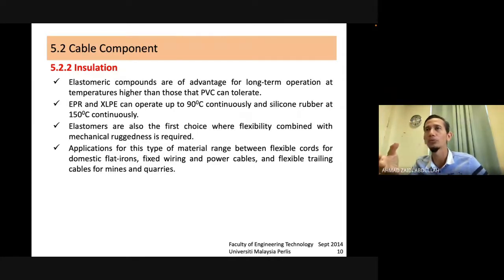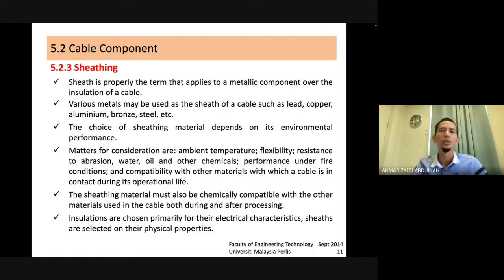Let's say your project just for makmal kan, for laboratory. And then you can see some lab it has isolators, maybe 20 or 30 isolators. So meaning that load requires a high ampere. So you must provide a very good cable to cover that load. If you just provide a very simple or low range of the cable, it will tend to short circuit. Okay. Alright. So sheathing pula.